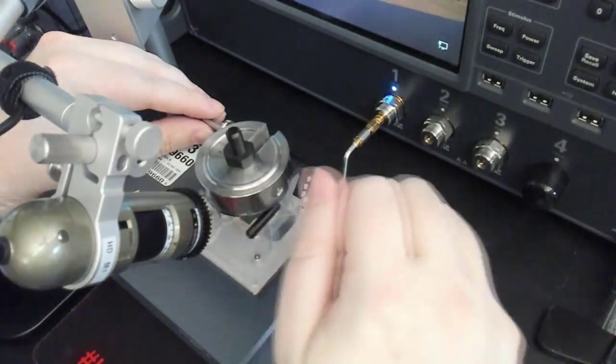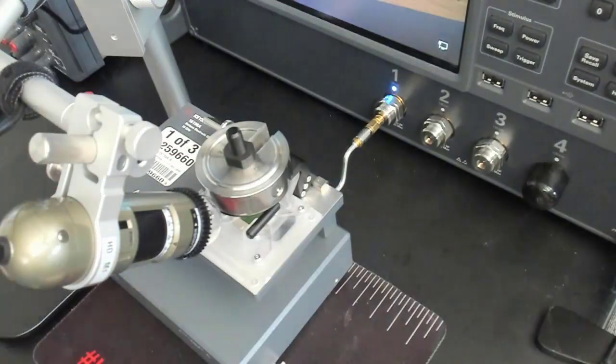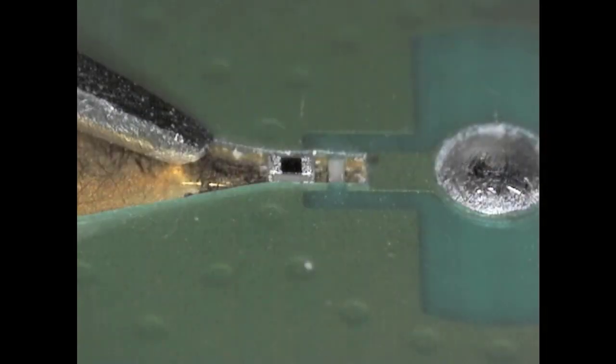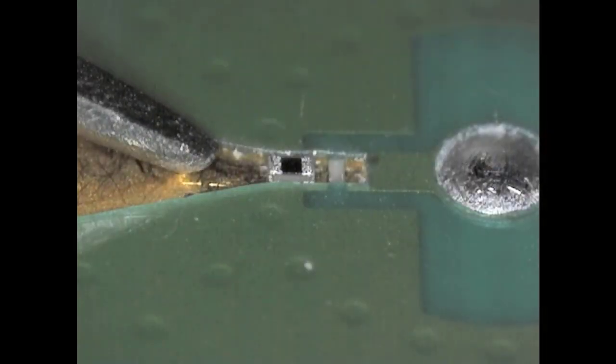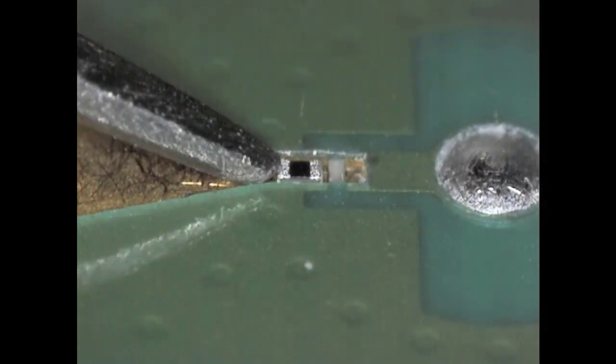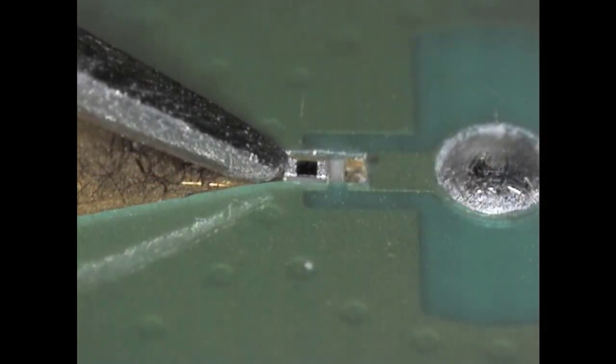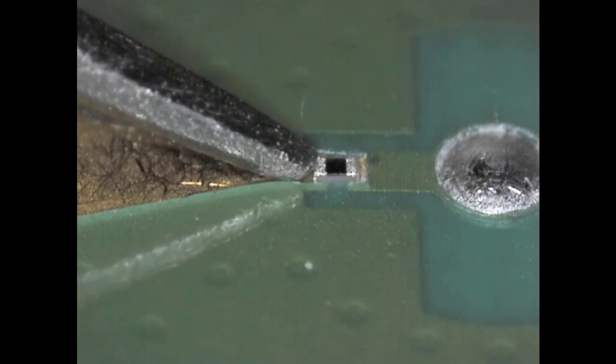With the system now calibrated, measuring devices is as simple as placing them across the contact board terminals and lowering the weight.